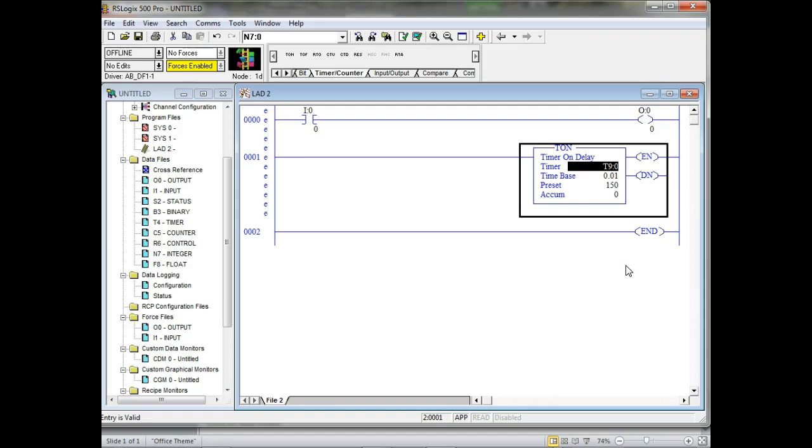And then the accumulator comes set to 0, guys, but you can set it anywhere you want to. By default, it's at what? 0. So you can start the timer timing from something besides 0. And we can address these registers too. We can address the preset register. It's a word. And we can address the accumulator, which means I can load this thing from anywhere.